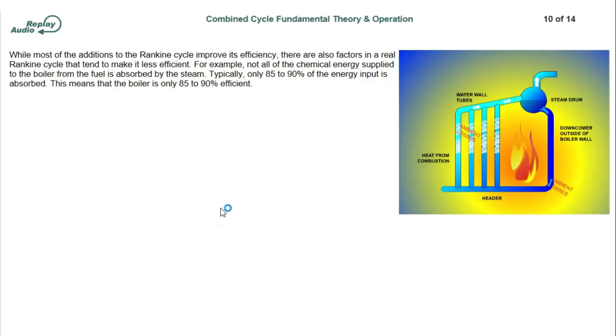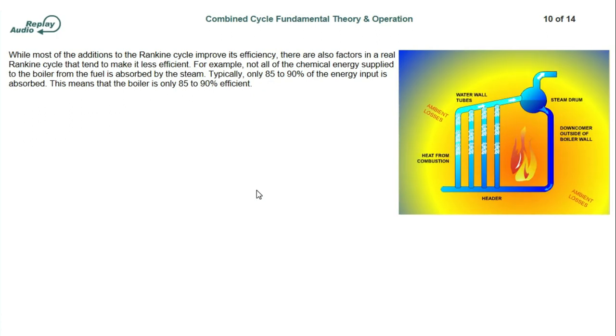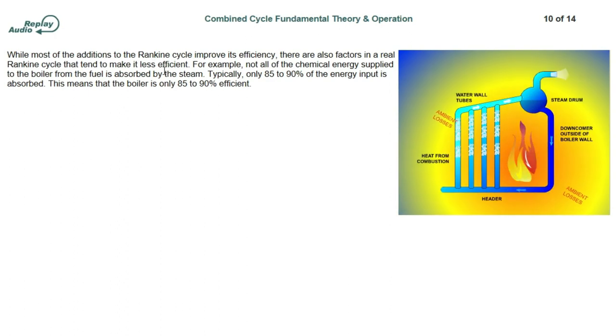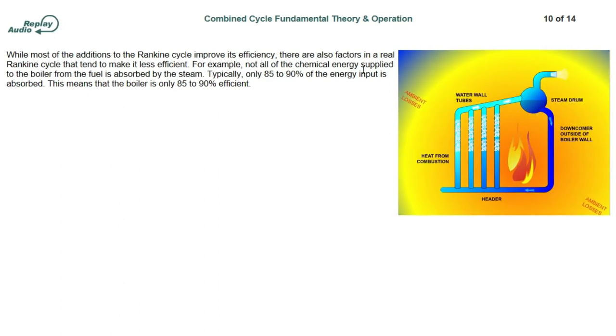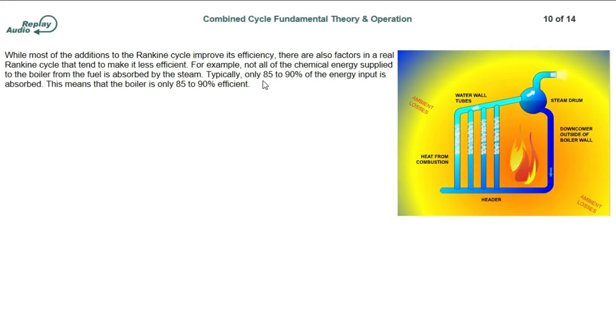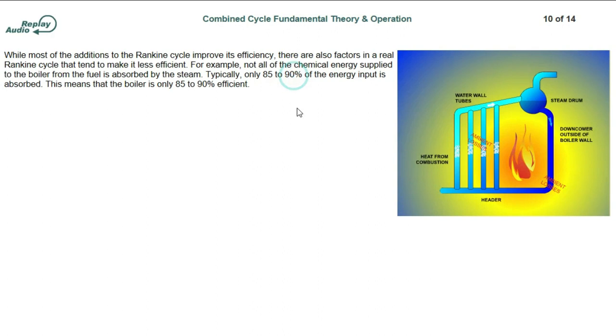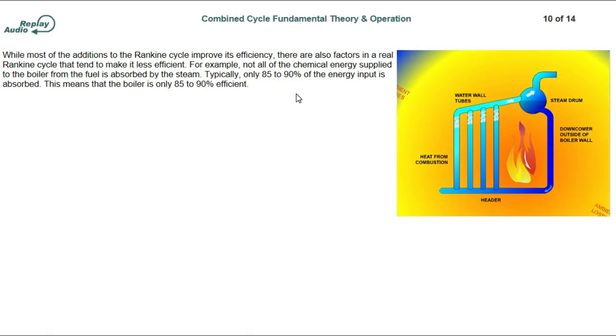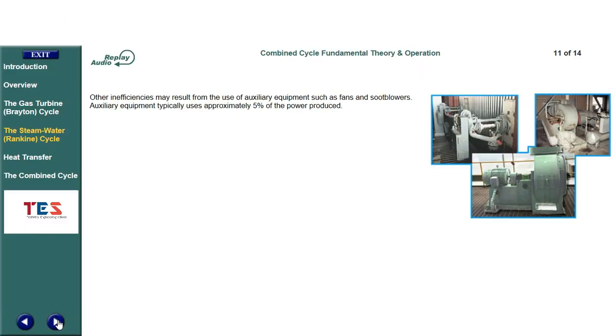Components such as feed water heaters and reheaters are added to improve cycle efficiency. While most additions to the Rankine cycle improve its efficiency, there are also factors in a real Rankine cycle that tend to make it less efficient. For example, not all of the chemical energy supplied to the boiler from the fuel is absorbed by the steam — typically only 85-90% of the energy input is absorbed, meaning the boiler is only 85-90% efficient. Other inefficiencies may result from auxiliary equipment such as fans and soot blowers, which typically uses approximately 5% of the power produced.